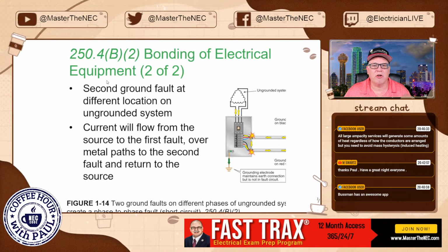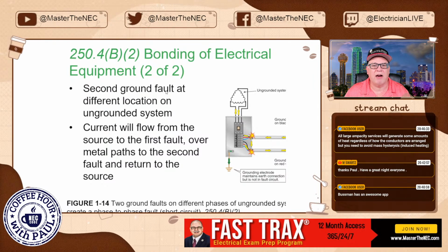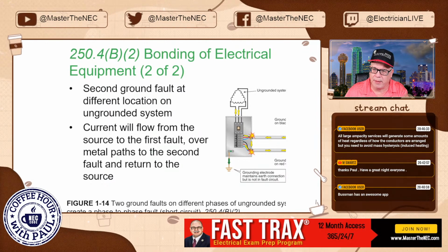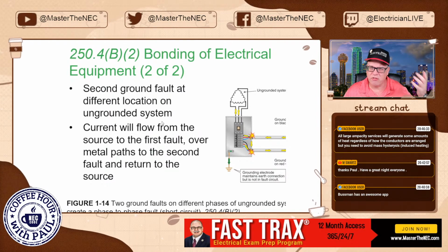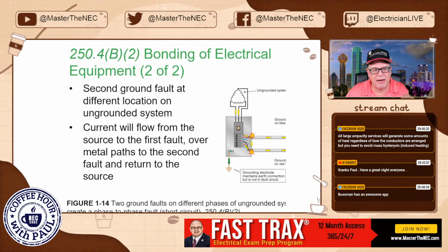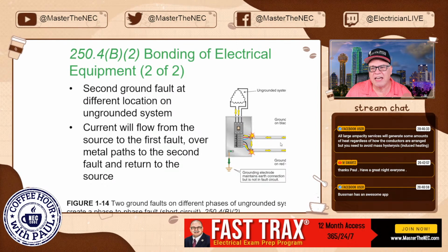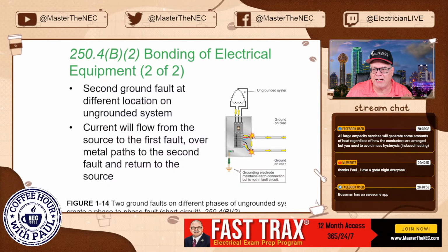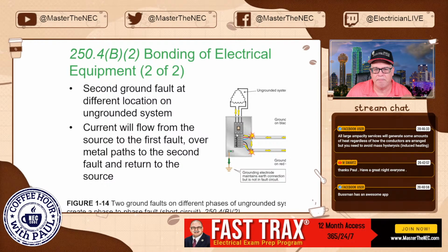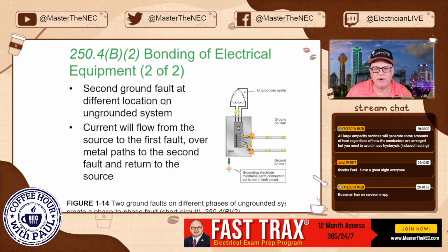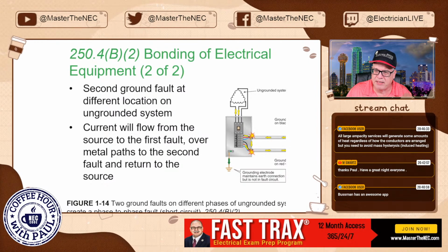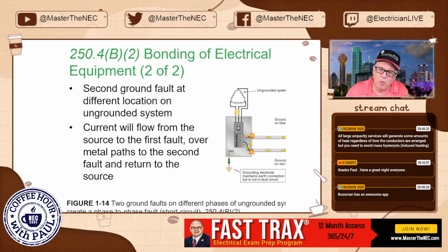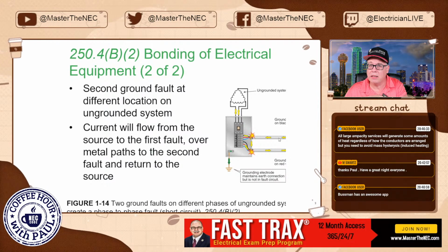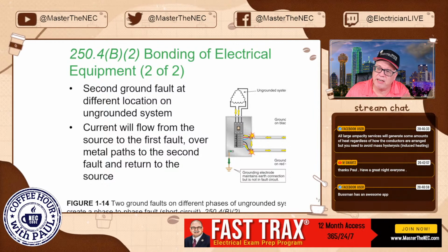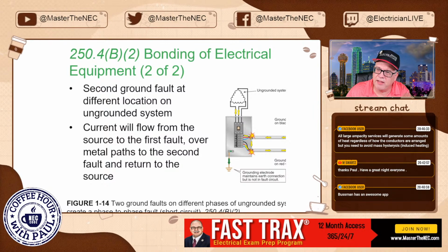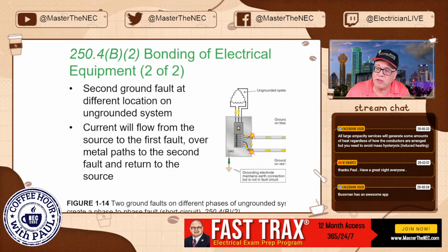Now, 250.4(B)(2), bonding of electrical equipment. Second ground fault. So that first ground fault, here was that first one, remember? I kind of gave it away a little bit earlier, but anyway, I get excited. So the second ground fault right here in this system. Okay, so the second ground fault on a different location on the ungrounded system. So this is the one that happened here, and then somewhere else, so this one didn't clear right away. This one down here happened at another location, and this one is in the black. This one happens to be in the red.